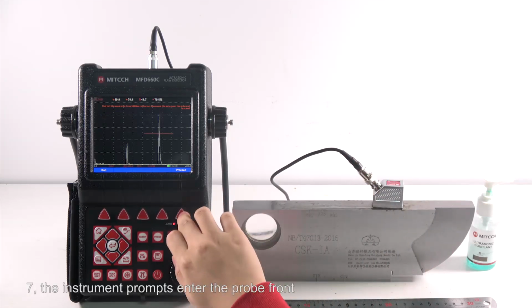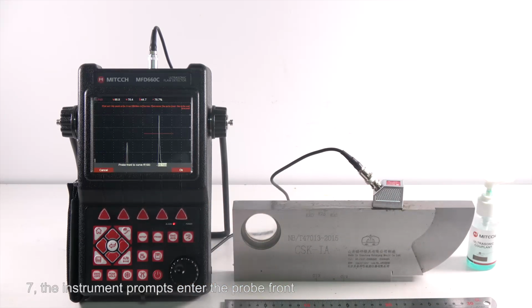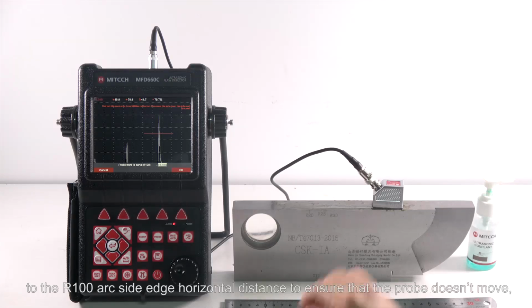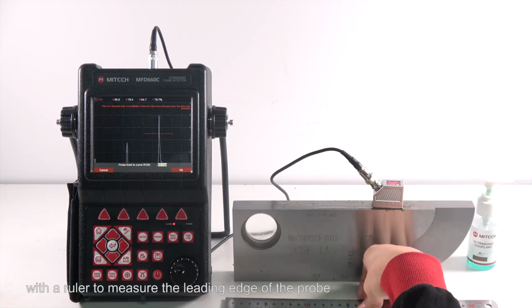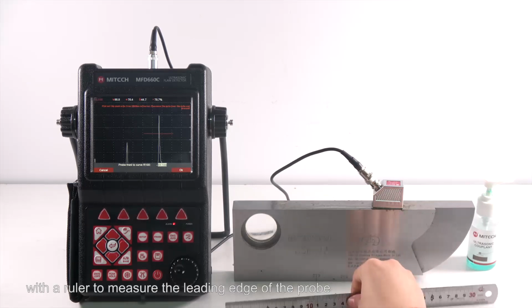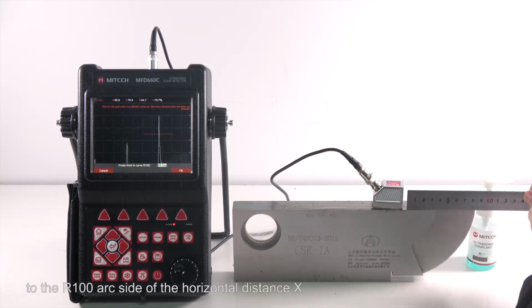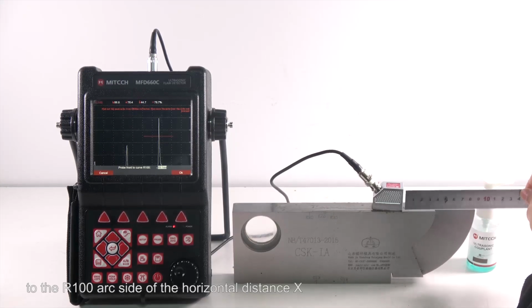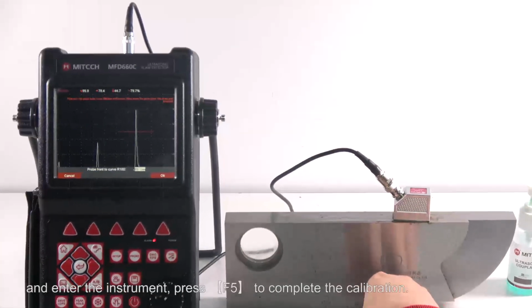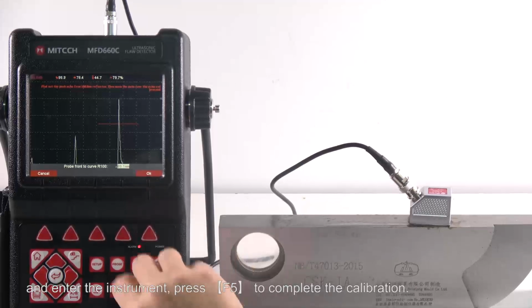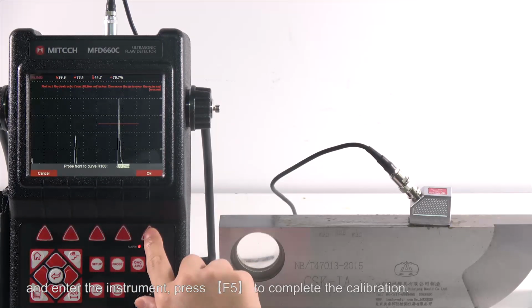The instrument prompts you to enter the horizontal distance from the probe front to the R100 arc edge. Ensure that the probe doesn't move. With a ruler, measure the horizontal distance X from the leading edge of the probe to the R100 arc edge and enter it into the instrument. Press F5 to complete the calibration.